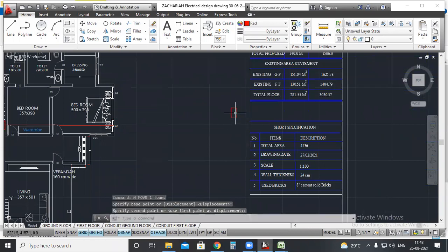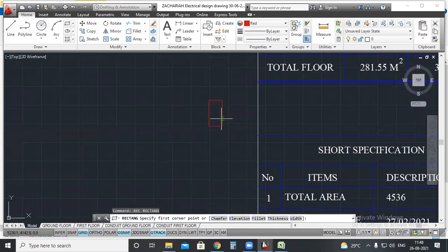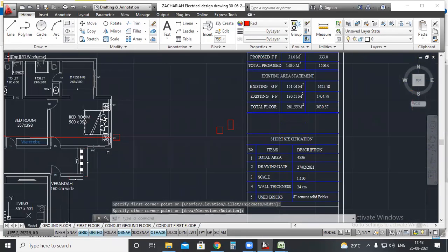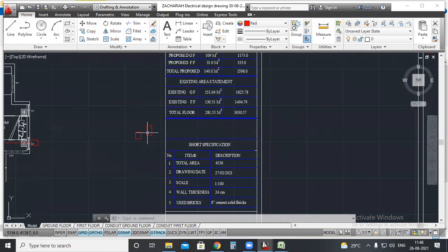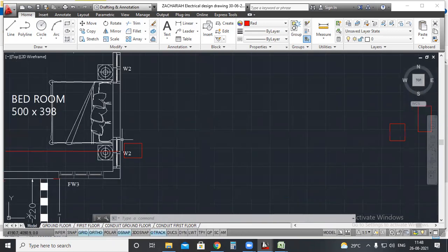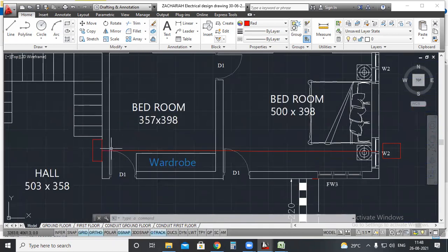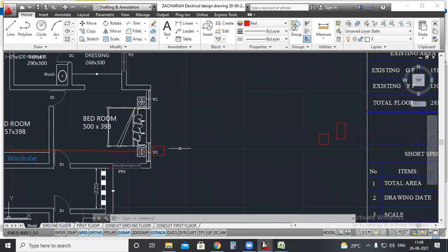the energy meter is located outside, on a compound wall, then you need to provide manholes here. Here also you need to provide a manhole. Just in case it is crossing a particular limit, like more than 30 meters, at the entry point and the starting point, you need to provide a manhole. The cable is running underground. But here I'm just saying from here to here, you just directly provide the underground cable to the DB. So then you can provide a 50 pipe.